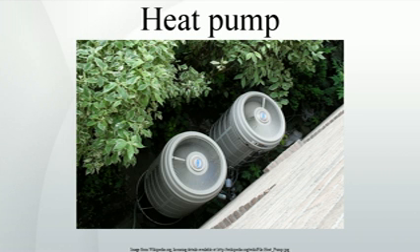In mild weather, COP may be around 4.0, while at temperatures below around 0 °C, 32 °F, an air source heat pump can achieve a COP of 2.5 or better, which is considerably more than the energy efficiency that may be achieved by 1980s heating systems, and very similar to state-of-the-art oil or gas heaters. The average COP over seasonal variation is typically 2.5-2.8, with exceptional models able to exceed 6.0 in very mild climate, but not in freezing climates.